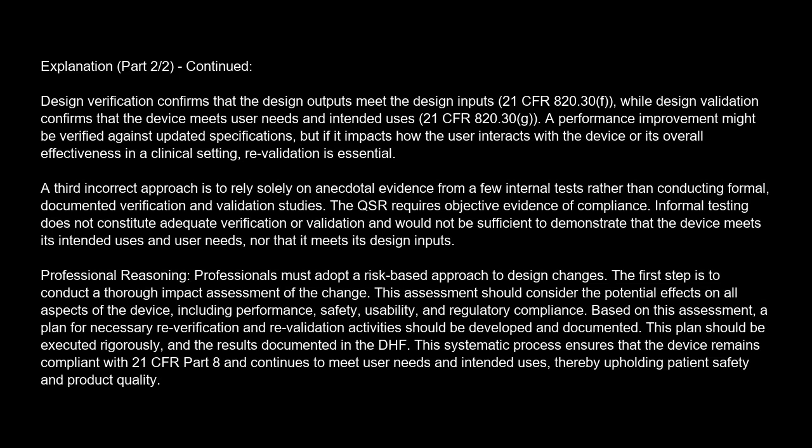Design verification confirms that the design outputs meet the design inputs, 21 CFR 820.30(f). While design validation confirms that the device meets user needs and intended uses, 21 CFR 820.30(g). A performance improvement might be verified against updated specifications, but if it impacts how the user interacts with the device or its overall effectiveness in a clinical setting, revalidation is essential.